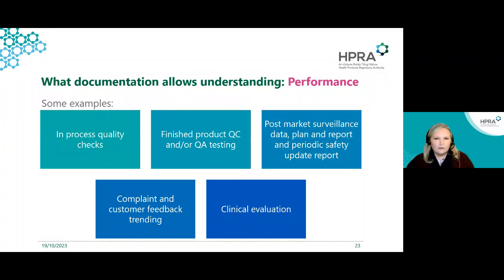Demonstrating the performance of the device and allowing an understanding sufficient to assess conformity can again be done in several ways. In-process and finished device testing can show that the device is operating as expected before it is placed on the market. Predefined tests and records of the completion of those tests for custom-made devices should be documented and kept along with all other manufacturing records.